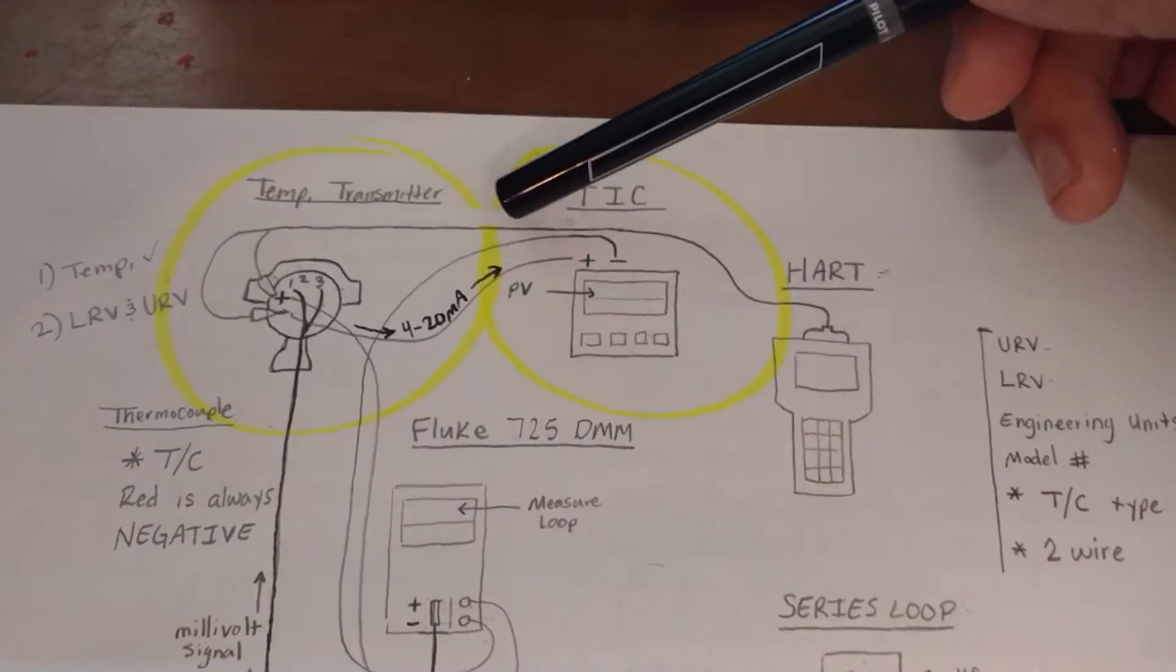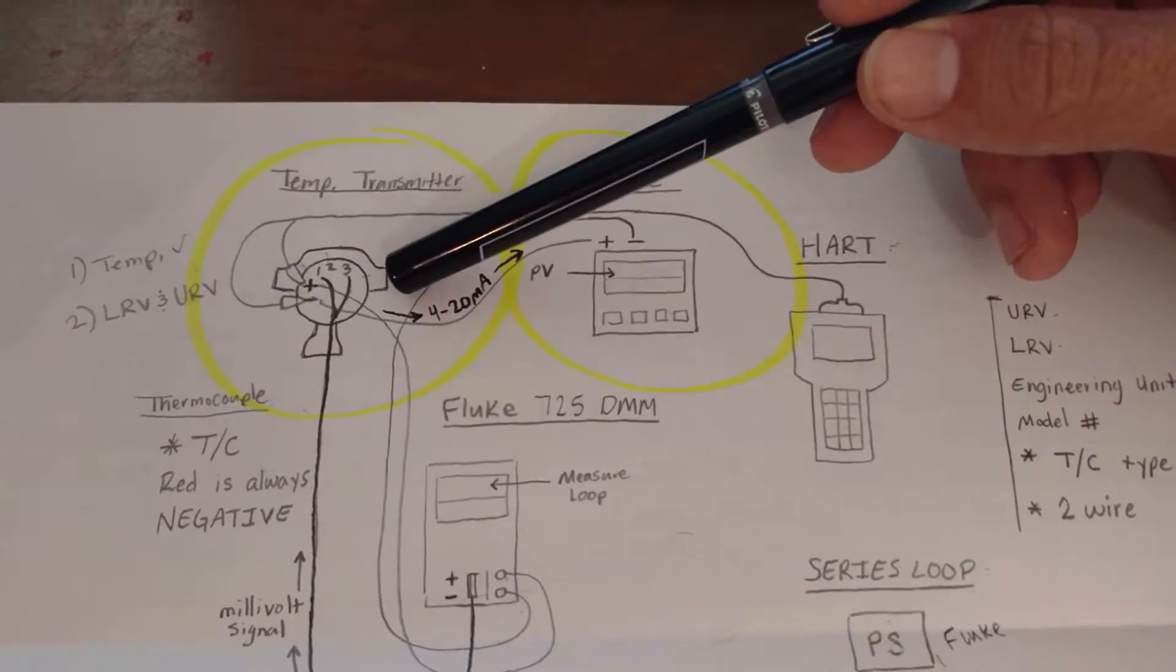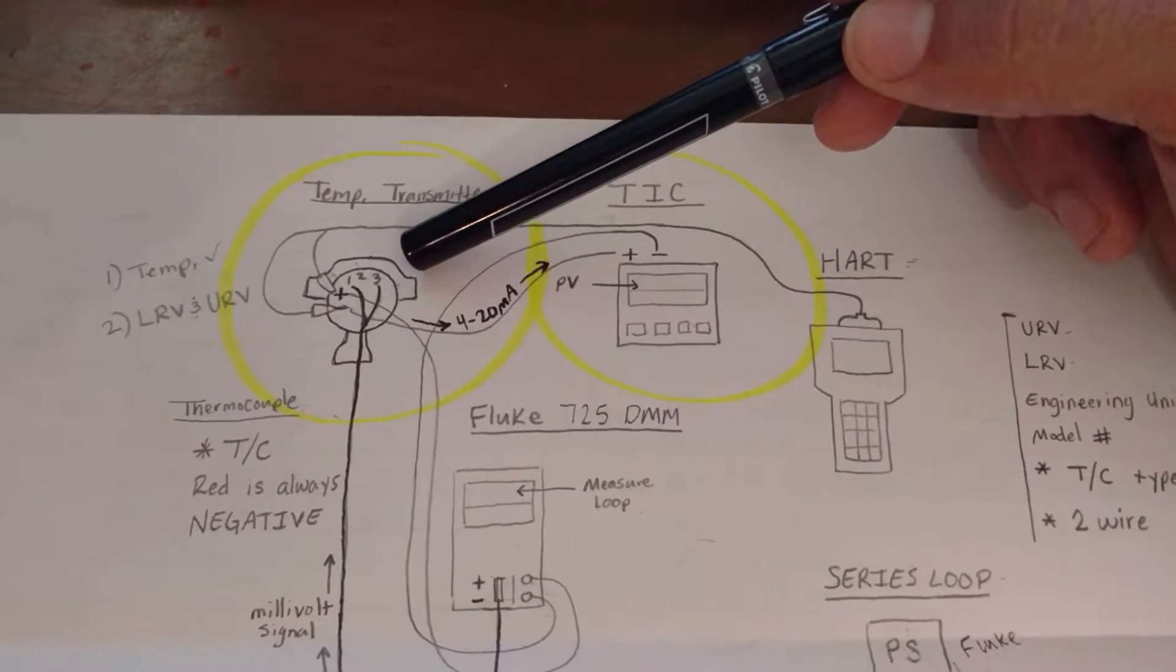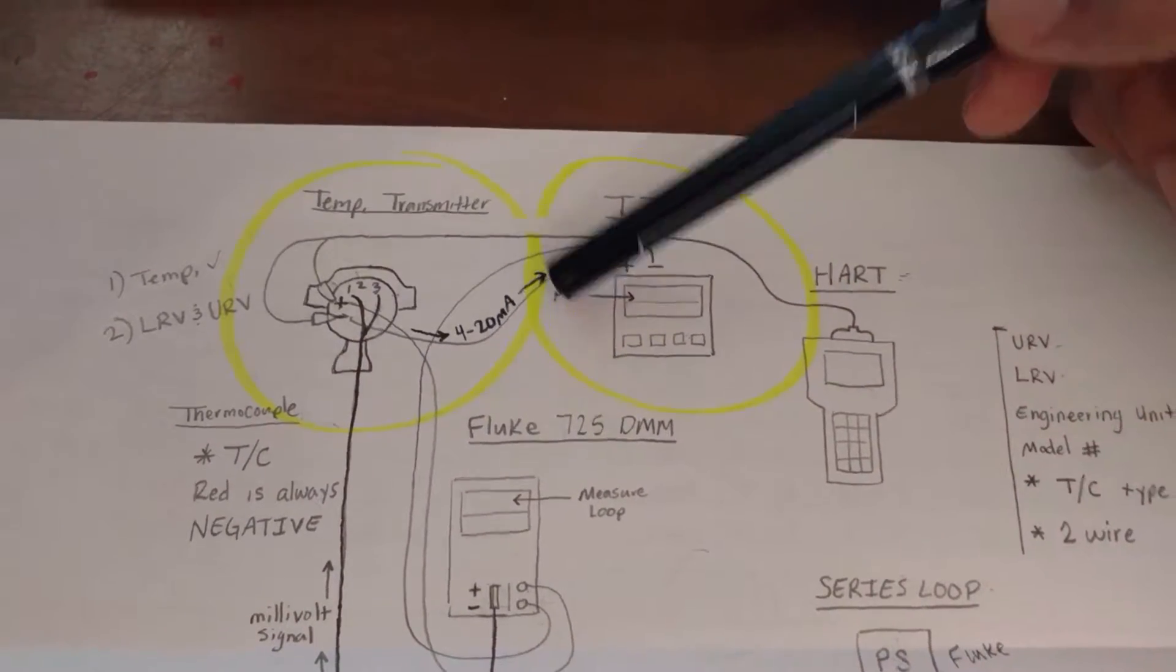It's going to take the millivolts and depending on the upper range value and lower range value that have been programmed into this transmitter, it's going to send a proportional milliamp signal to another device.